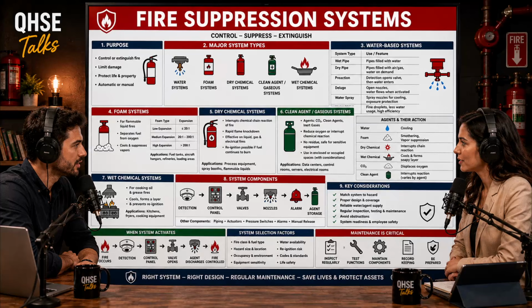And from a facility management standpoint, their big selling point was that they leave zero residue, right? It was revolutionary. You could have a fire in a room full of mainframe computers. The halon system would put out the fire in seconds and you just ventilate the gas out. The computers would still be running perfectly, no water damage, no corrosive powder. But as with all wonder drugs, there is a massive catch. Two catches. First, when halon is exposed to the extreme thermal energy of the flames, it decomposes into highly toxic byproducts, like hydrogen fluoride gas, which is dangerous to breathe.